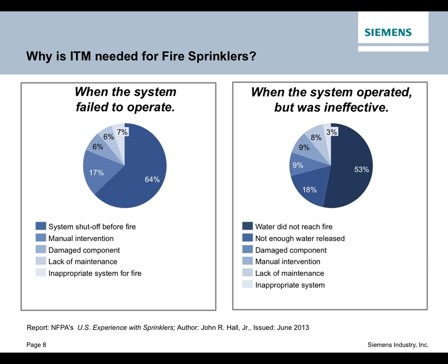Other leading causes include manual intervention that defeated the system. That's when somebody went in and shut the system off too soon. Or it could be damaged components, lack of maintenance, and an inappropriate system for the type of fire that was there. And when sprinklers operated, on the chart on the right, but were ineffective, the reason usually had to do with insufficient water supply being applied to the fire. So the key point here is that when a fire sprinkler system fails, 2/3 of the time it's because the valve that controls the water was closed instead of being open. And when the systems operate but were not effective, about 1/2 of the cases, it is because the water did not reach the fire. This could be due to such things as partially closed valves. So it's not completely closed, it's just partially closed.